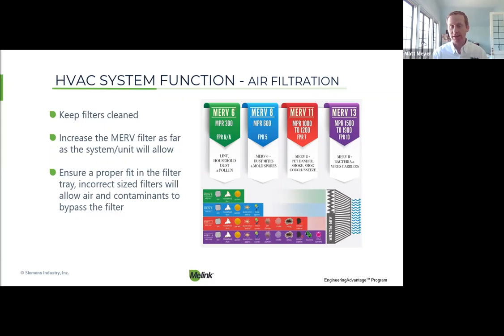Right now, specifically with COVID-19 going on, there's a lot of recommendations, and most bodies are recommending the use of the MERV 13 filter. If you can see the chart very clearly, I know it's kind of small, you can see that there's lots of different MERVs out there. And there's even more than just these 4. There are actually MERVs beyond the MERV 13. MERV 13 is the first MERV level where it starts to capture bacteria and virus carrying sizes. And so that tends to be the first one that gets thrown out there. The higher that number gets, obviously the more expensive, and the lower on the supply chain you'll be able to find them too. There's probably less of them out there.